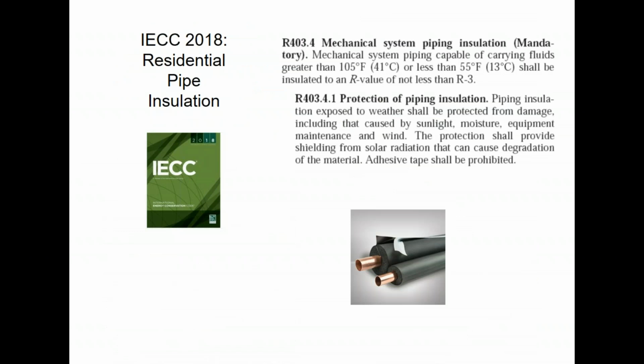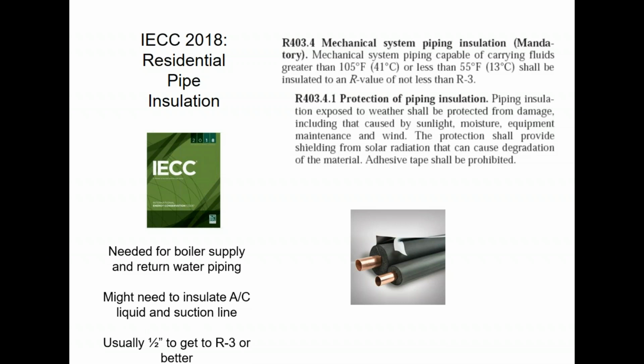Piping systems. Just like ductwork, piping systems need to be insulated. What are the rules for insulating them? If you see up there at the top, any mechanical piping. What's mechanical piping? It's boilers, chillers, refrigerant lines, things like that, right? So any mechanical piping that's carrying a fluid, meaning water, refrigerant, water and glycol, if the temperature of the fluid is above 105 degrees, i.e. it is heated fluid, then you have to insulate. If it's below 55 degrees, i.e. it is cooled fluid, then you have to insulate it, right?